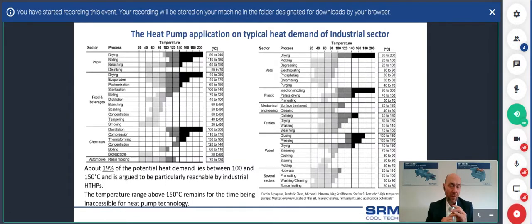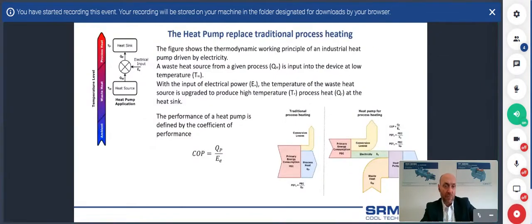For the moment, we will not evaluate the applications above 150 degrees C because there are some limitations regarding the heat pump technology. So when we identify the heat pump process, we can very simply put our system in this graph that illustrates where it is positioned, starting from the ambient temperature, the waste heat level, and the process heat. The heat pump process is positioned exactly in this area: it takes heat from the waste heat source, and through the input of electrical power, it produces higher level temperature fluids.